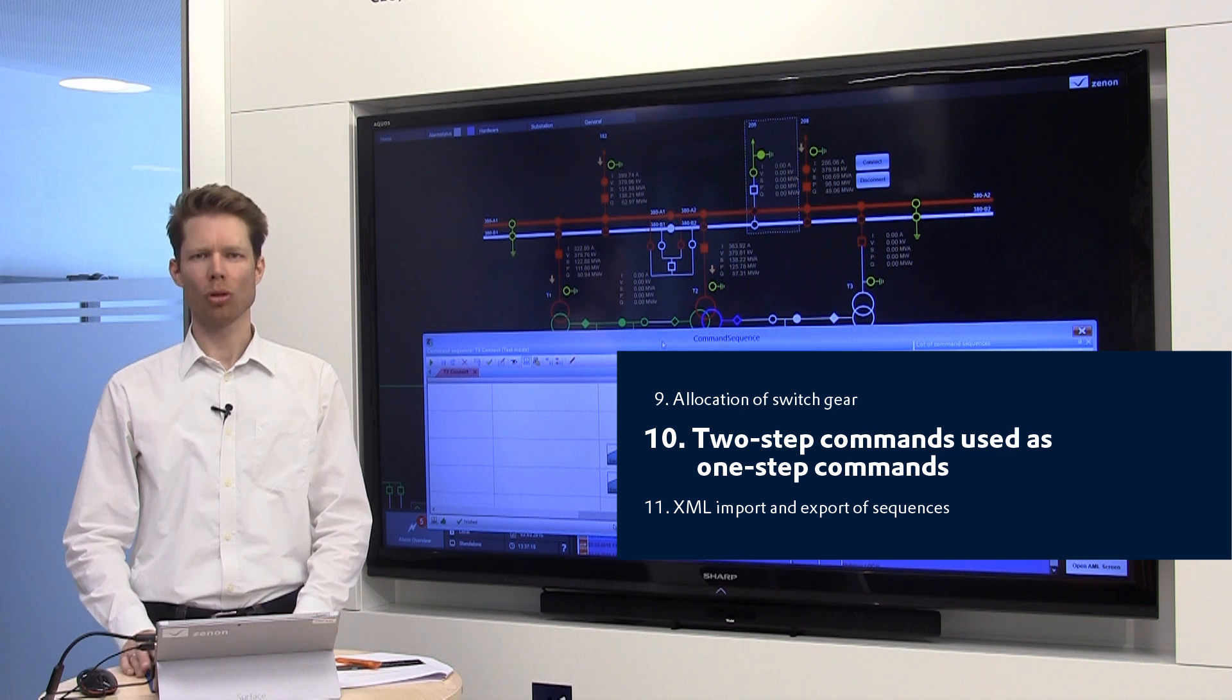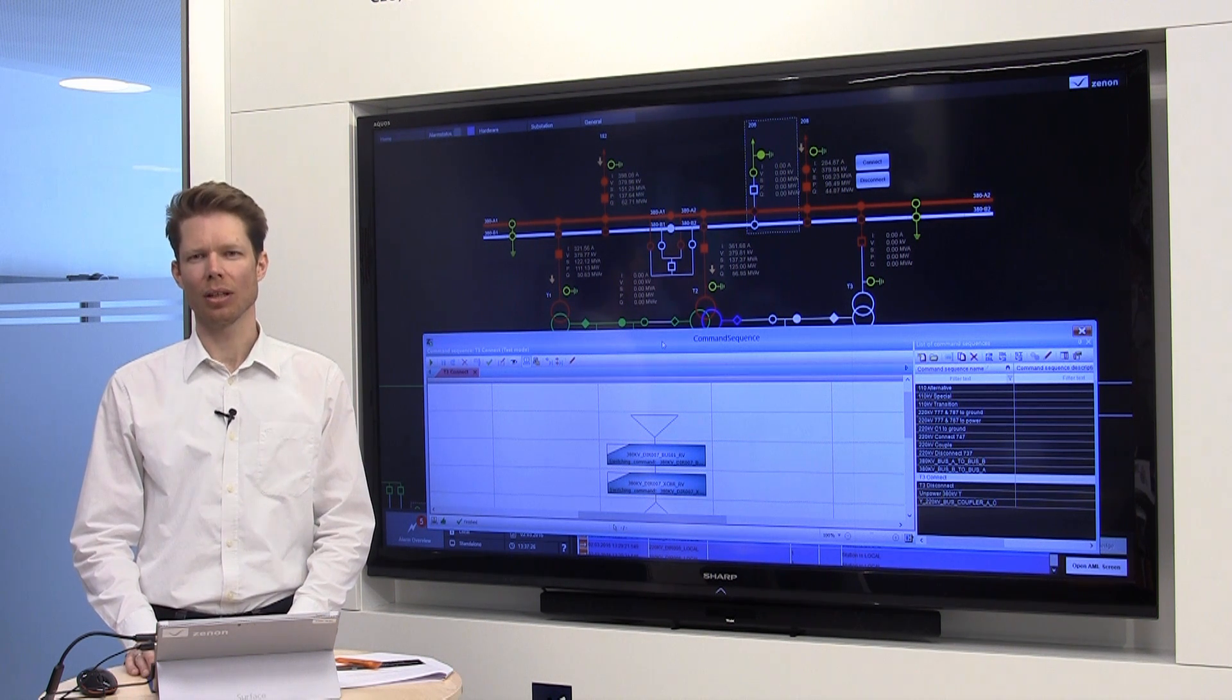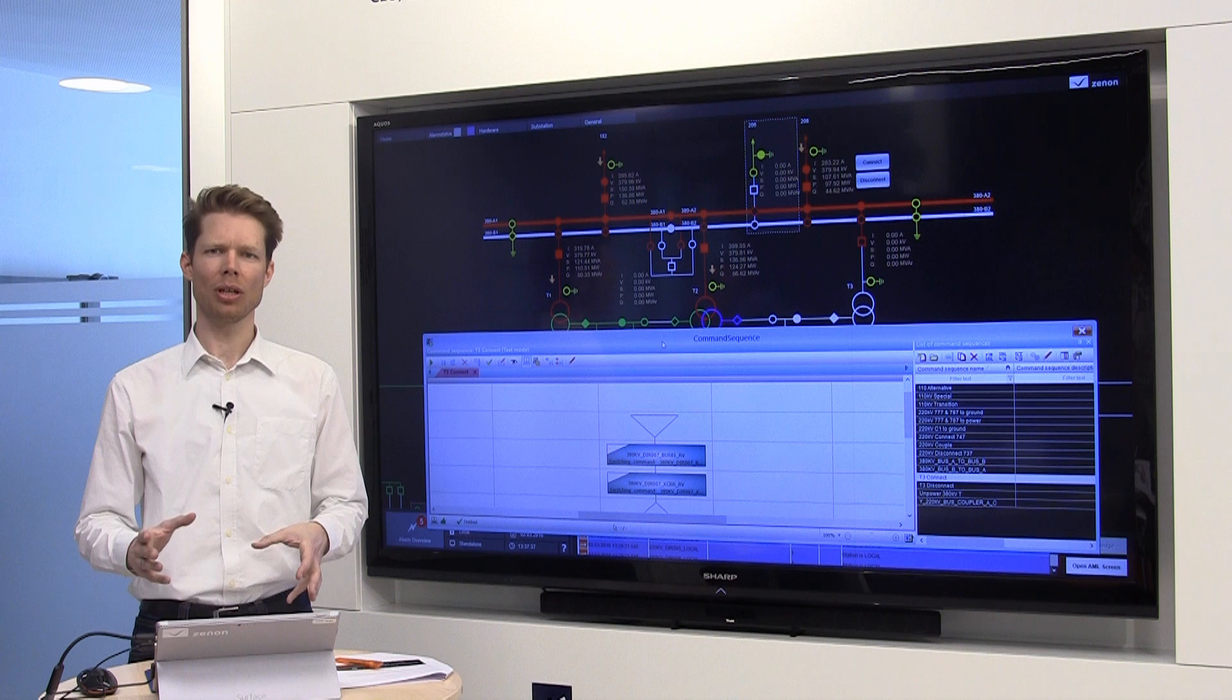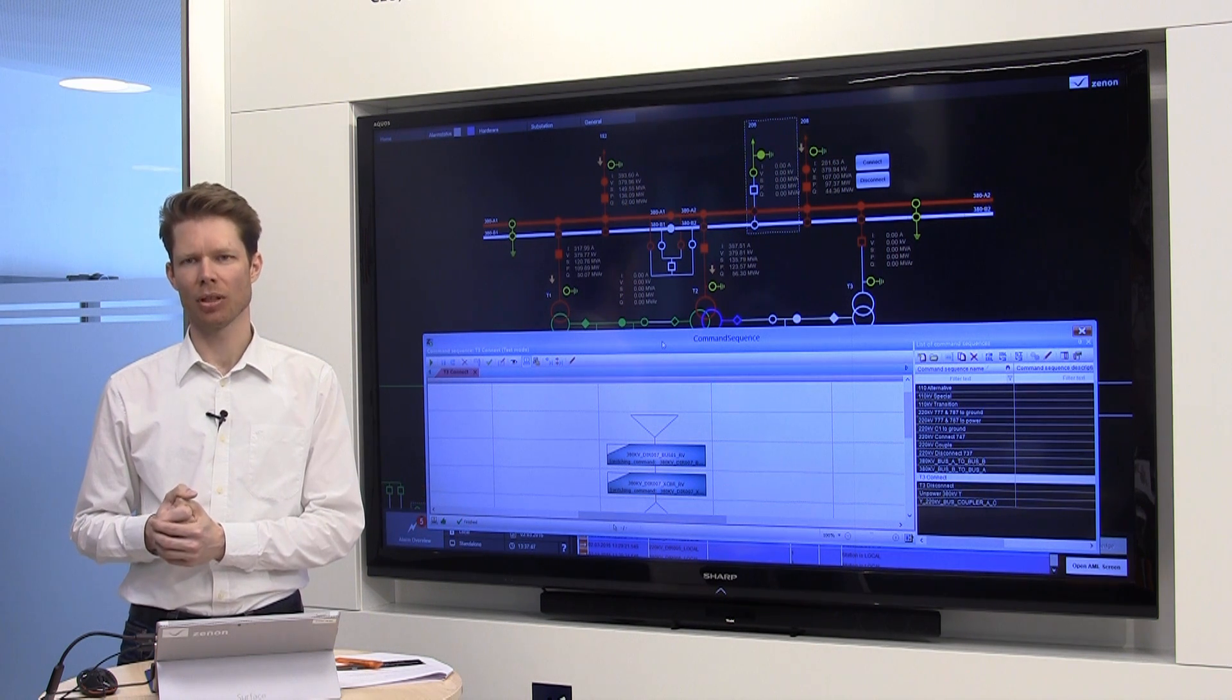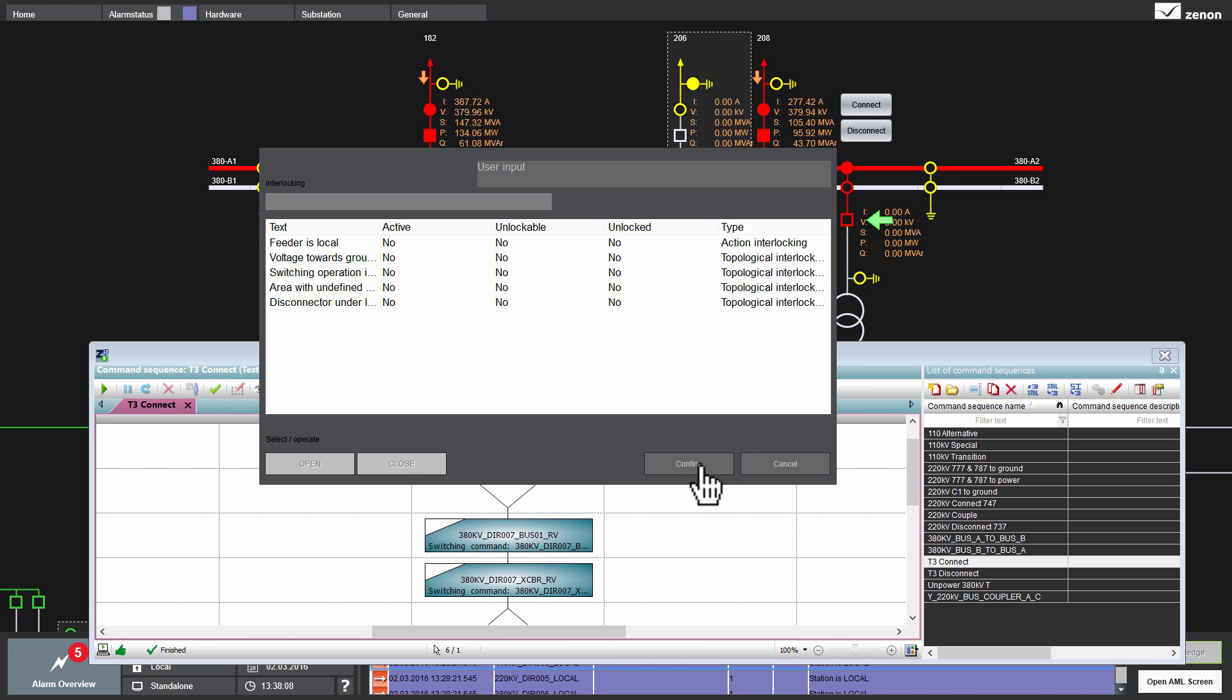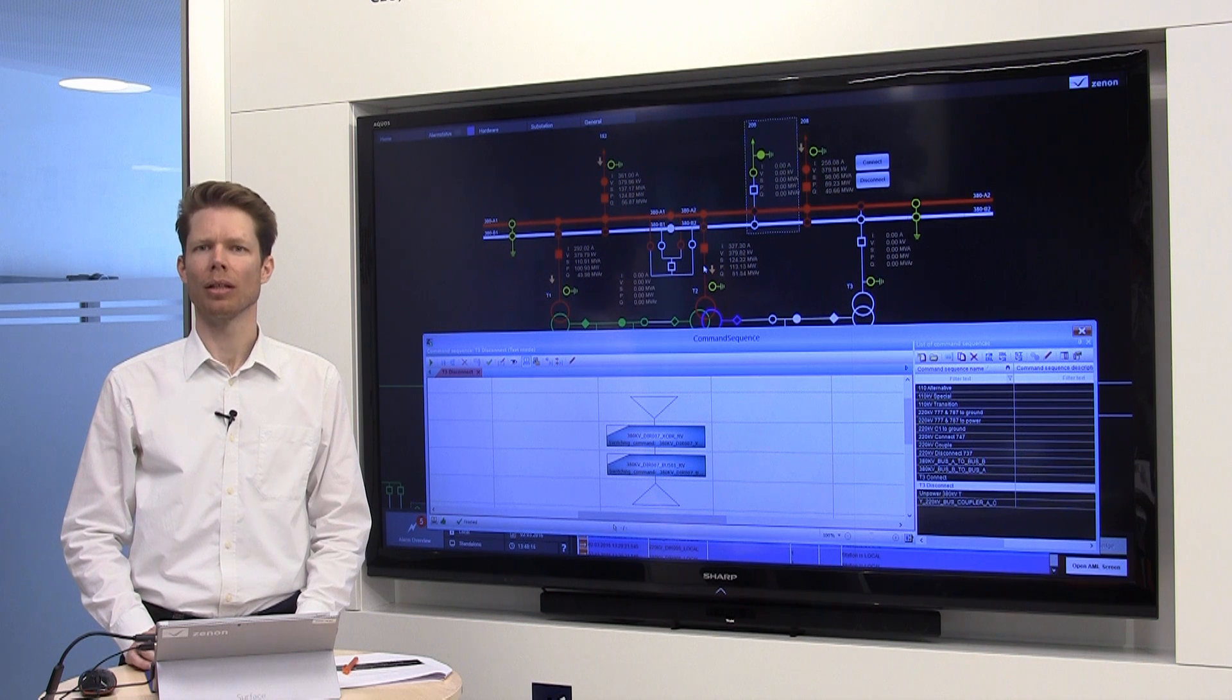Manual control commands can be either one-step or two-step commands. If you have a two-step command, this means that you need an additional user action to execute this. This can be a problem in a command sequence. That's the reason why we have implemented a feature where you can tell the system either to use a two-step command only in manual mode or if you use the same command in the sequence, use it as a one-step command like I show you here. I want to close this circuit breaker and now I have to confirm that with an additional mouse click. If you do that with the command sequencer, it works without a manual interaction.